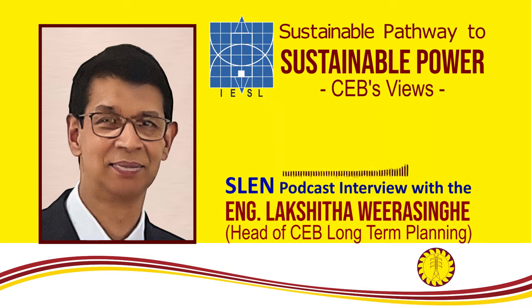As we all know, from the day we decided alternating current, or AC, as the best choice to transmit and distribute electricity, we have inherited what is known as a synchronous power grid, with synchronous generators running in synchronism, supplying the customer demand. In such a grid, the supply of electrical power, measured in megawatts, must be exactly equal to the demand for electrical power in real time. If this supply and demand balance is not maintained in real time, megawatt to megawatt, that affects the system frequency, which is maintained within a very narrow and tight band.